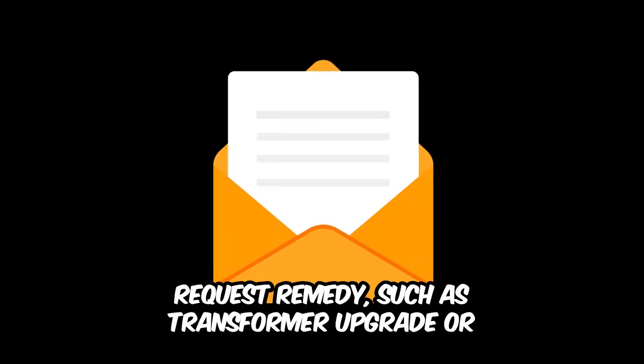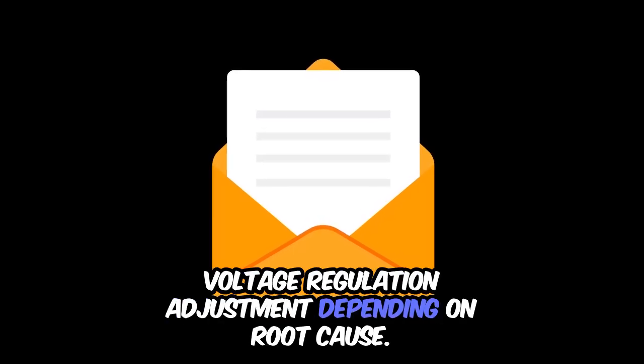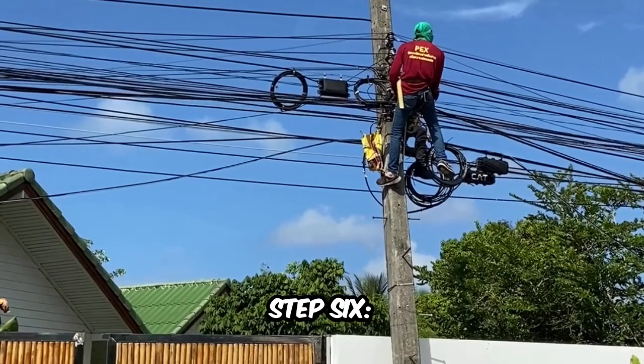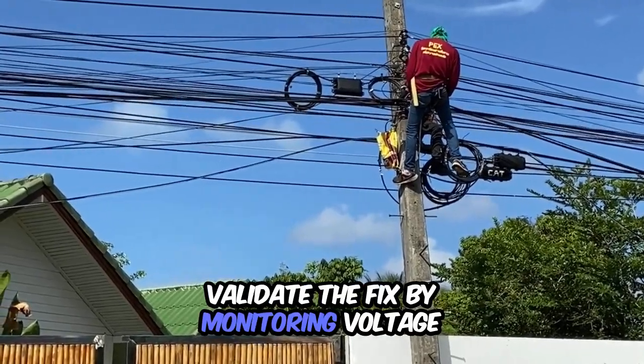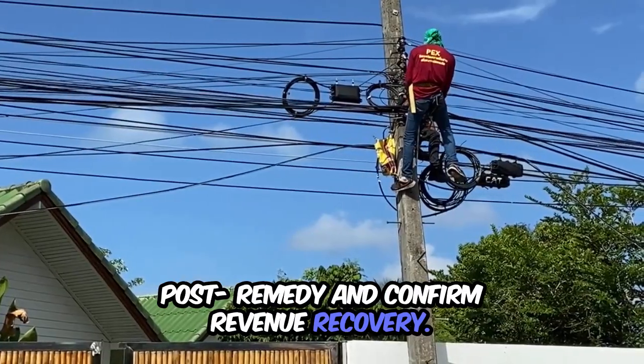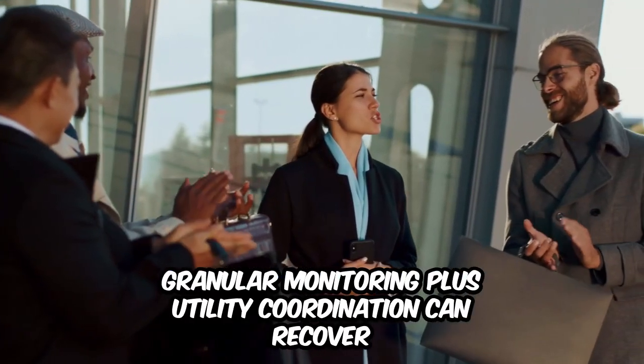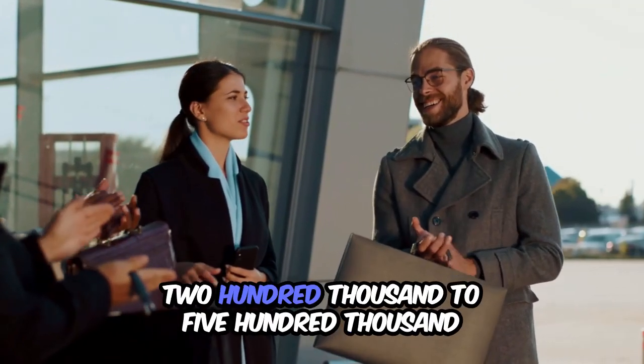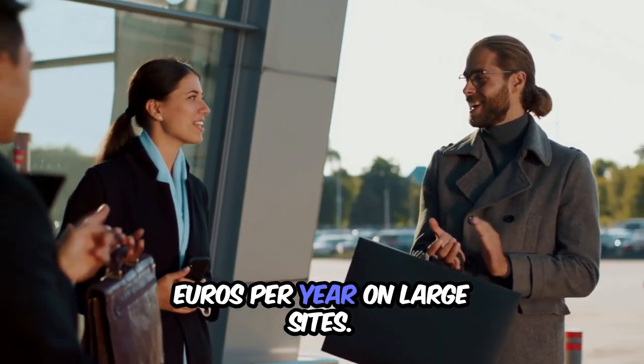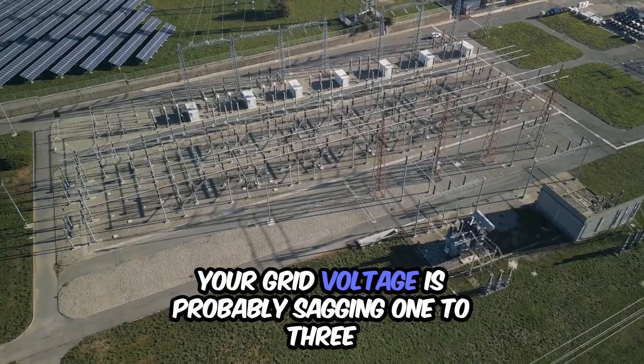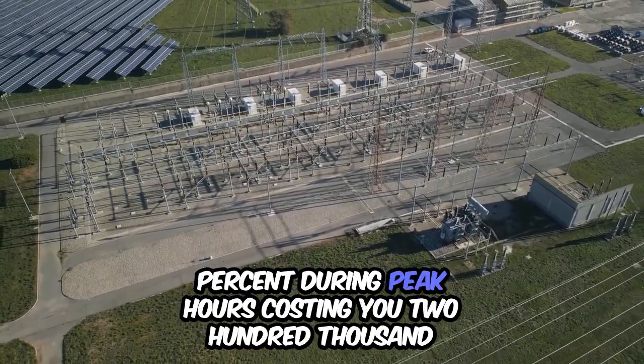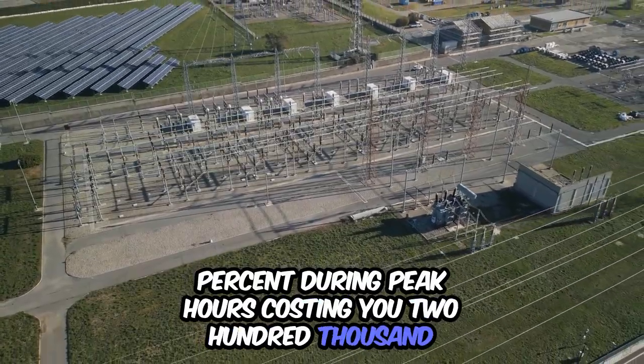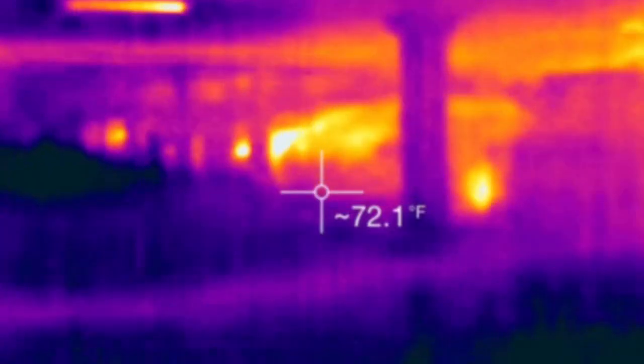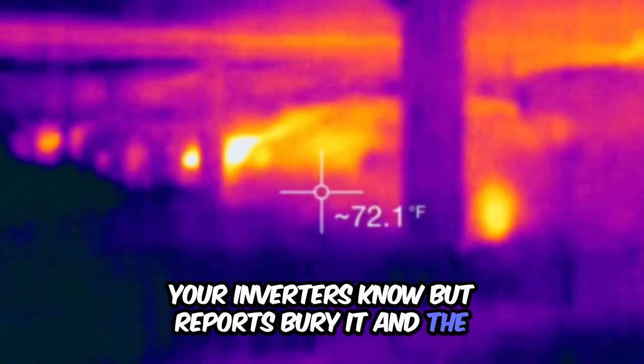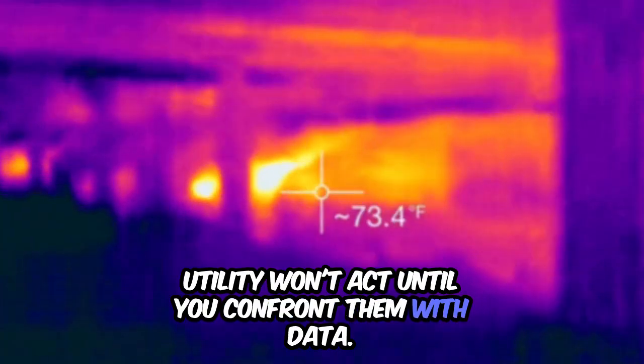Step 5. Request remedies such as transformer upgrade or voltage regulation adjustment depending on root cause. Step 6. Validate the fix by monitoring voltage post-remedy and confirm revenue recovery. Granular monitoring plus utility coordination can recover 200,000 to 500,000 euros per year on large sites. Your grid voltage is probably sagging 1 to 3% during peak hours, costing you 200,000 to 500,000 euros per year. Your inverters know, but reports bury it, and the utility won't act until you confront them with data.